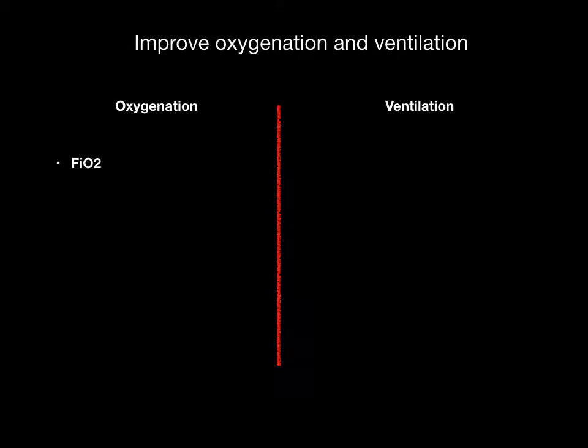The other thing you can adjust is the PEEP. PEEP is essentially the same as CPAP — it's a constant pressure delivered to the patient that stents the airways open. This pressure is measured in centimeters of water, and a typical number is about five or six.